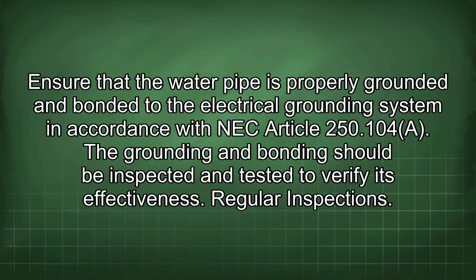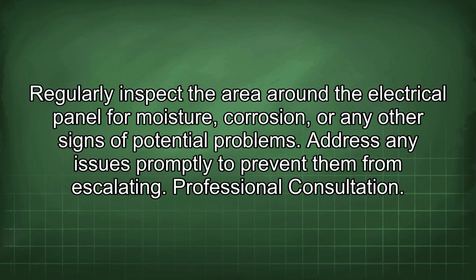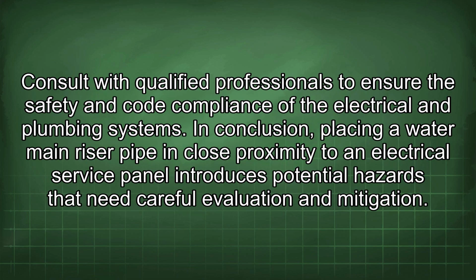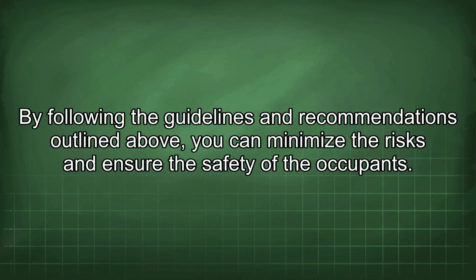Grounding and bonding. Ensure that the water pipe is properly grounded and bonded to the electrical grounding system in accordance with NEC Article 250.104(A). The grounding and bonding should be inspected and tested to verify its effectiveness. Regular inspections. Regularly inspect the area around the electrical panel for moisture, corrosion, or any other signs of potential problems. Address any issues promptly to prevent them from escalating. Professional consultation. Consult with qualified professionals to ensure the safety and code compliance of the electrical and plumbing systems. In conclusion, placing a water main riser pipe in close proximity to an electrical service panel introduces potential hazards that need careful evaluation and mitigation. By following the guidelines and recommendations outlined above, you can minimize the risks and ensure the safety of the occupants.